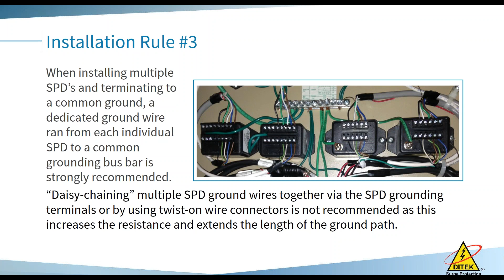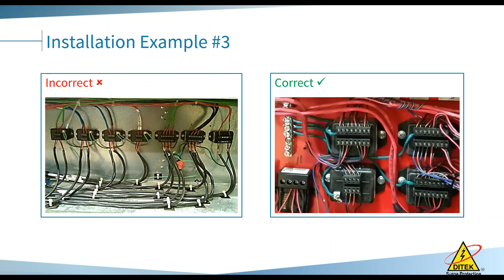Installation rule number 3, you don't want to daisy chain devices together. You want a common ground bus. That's important. And then you want a thicker gauge wire from that ground bus taking you to earth ground. This is no good. This is a better installation run into a ground bus.